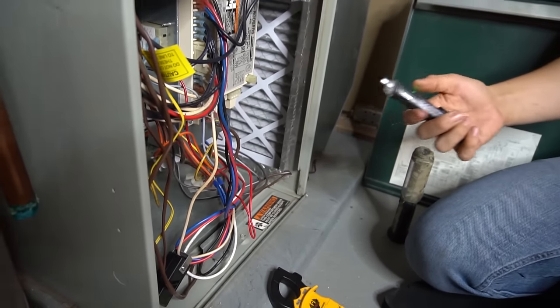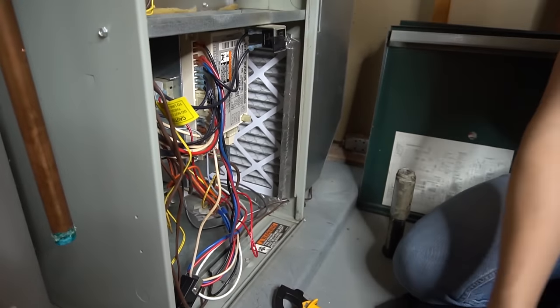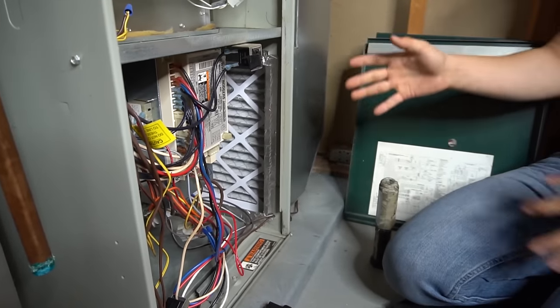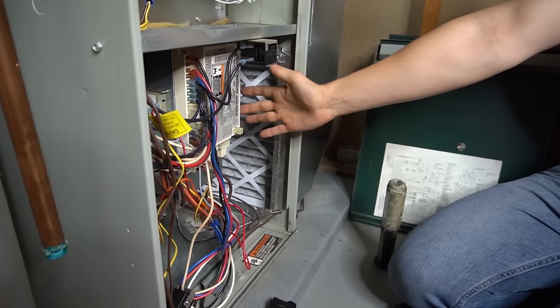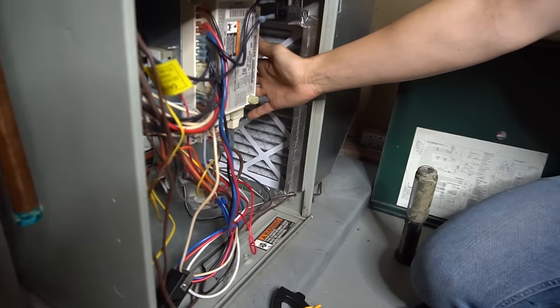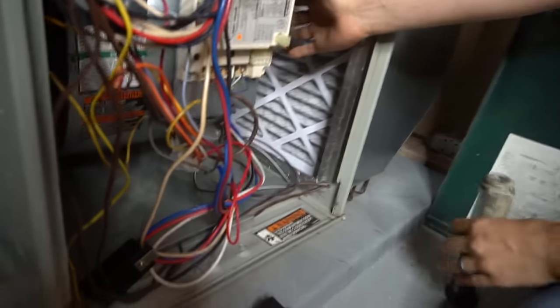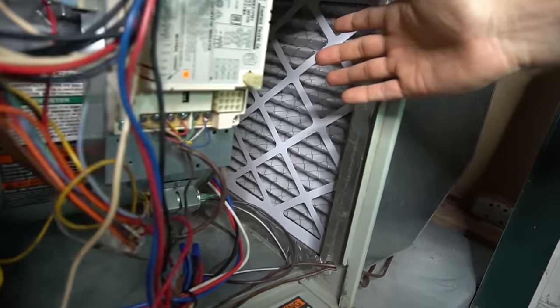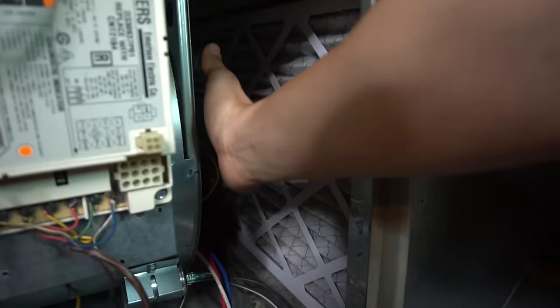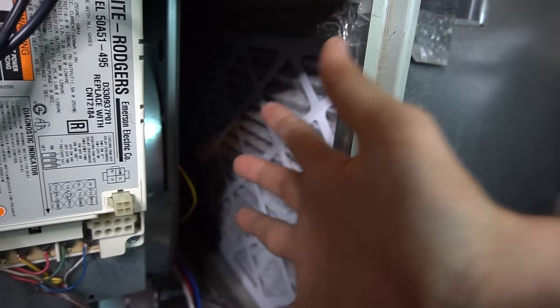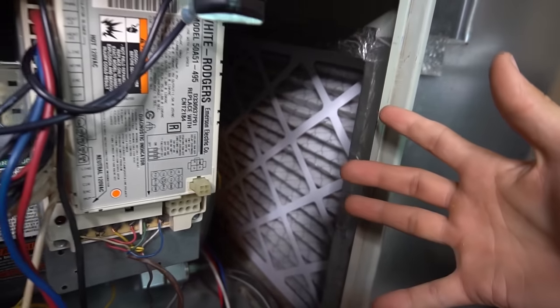So now that I've verified there's no power, just take your furnace doors off. If you reach in on the motor side, which is typically on the right side, and just grab the motor, a lot of times if it's been trying to start, the motor will be super hot.